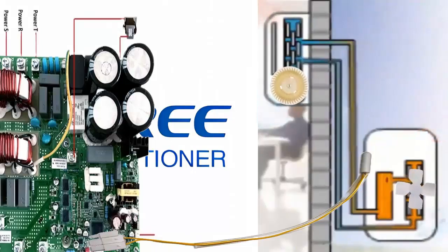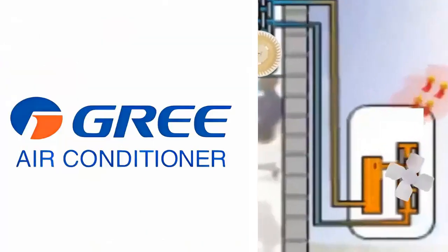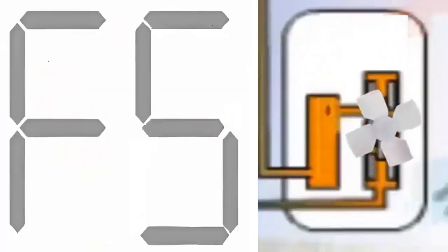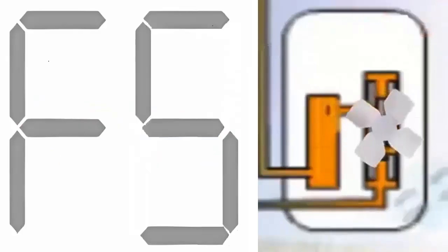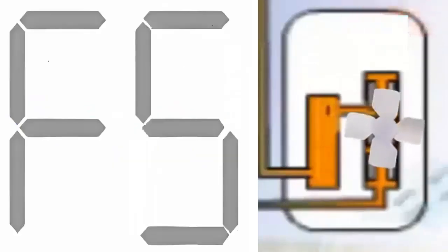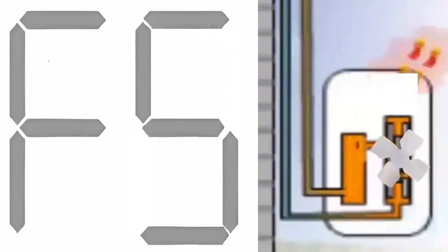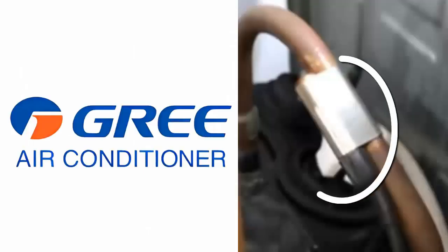Code F5 indicates a problem with the refrigerant discharge temperature sensor at the compressor outlet. This sensor is located on the thinner pipe of the compressor in the outdoor unit. If the issue is a significantly higher than normal discharge temperature, it is recommended to check the proper operation of the outdoor unit's fan, rule out refrigerant overcharge, and ensure the outdoor coil is clean.